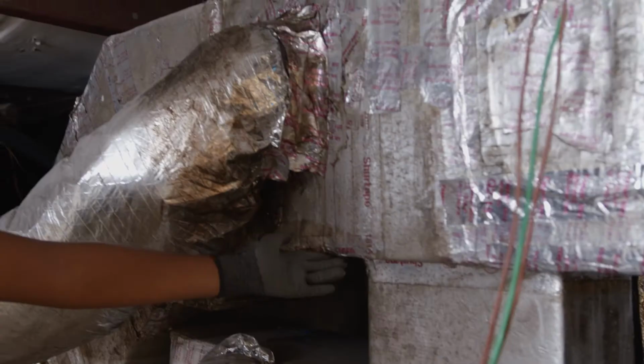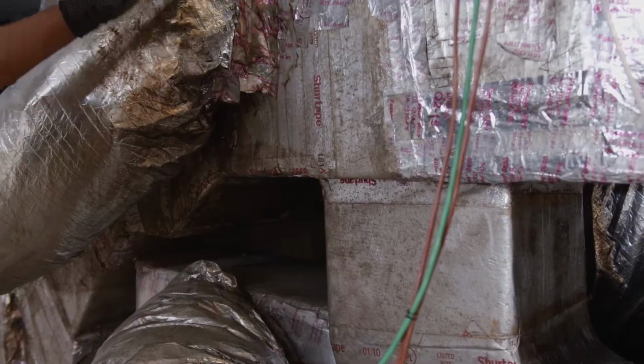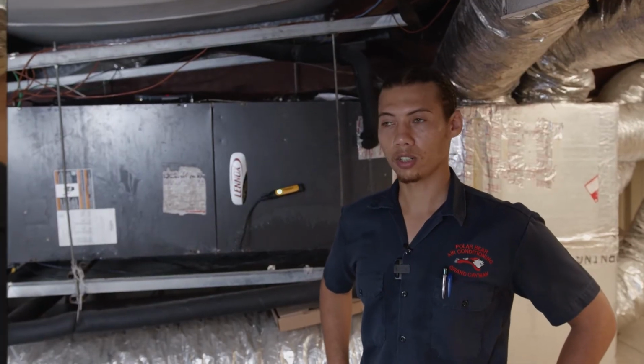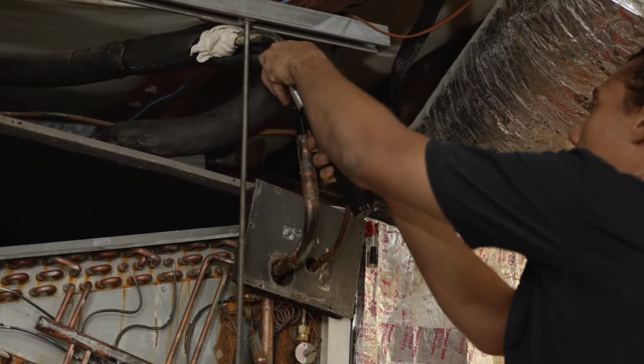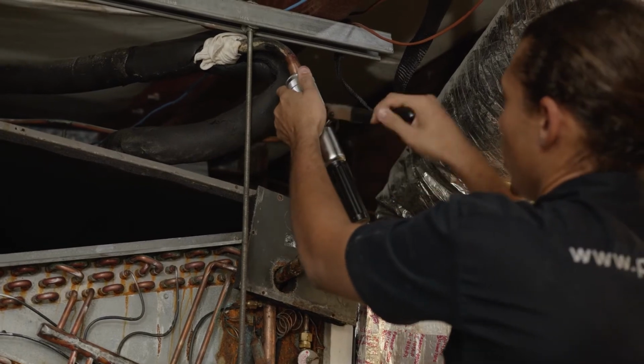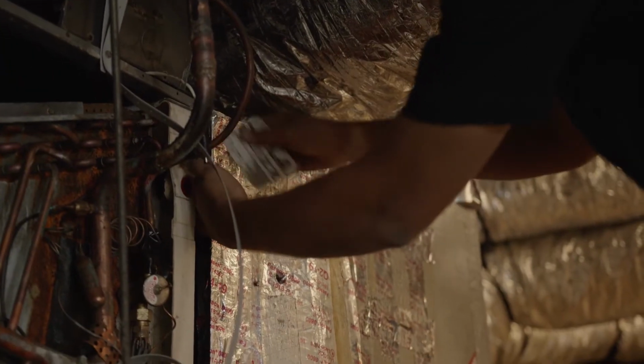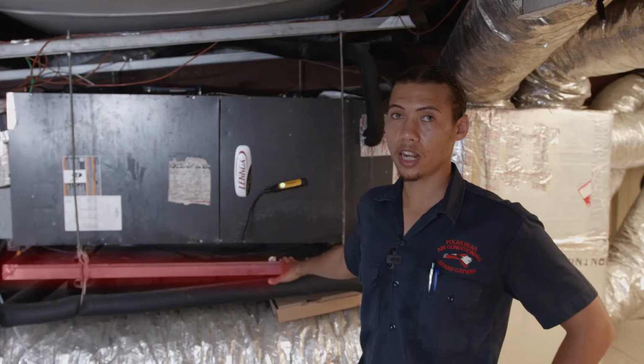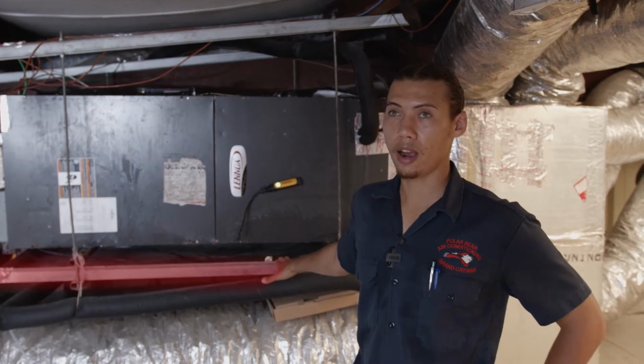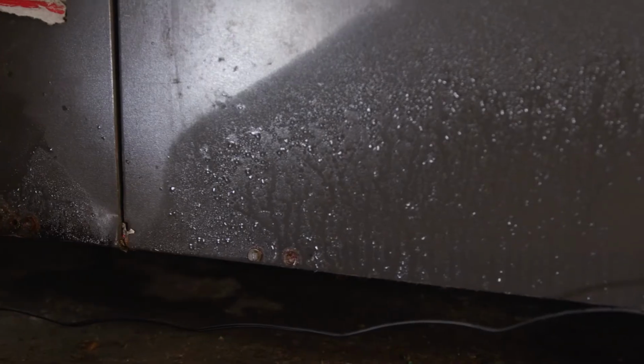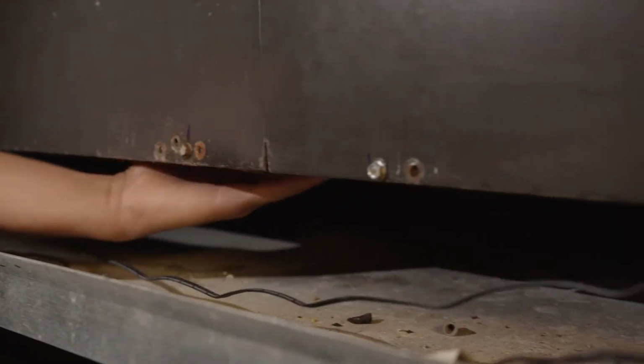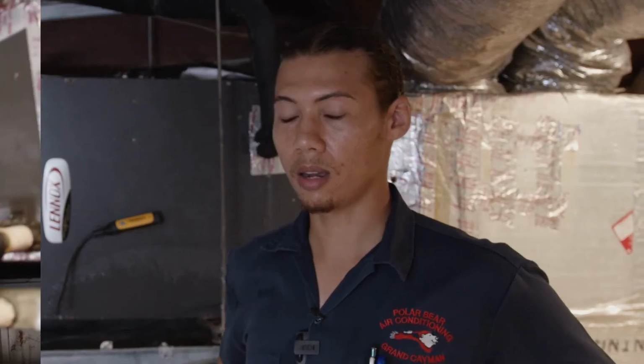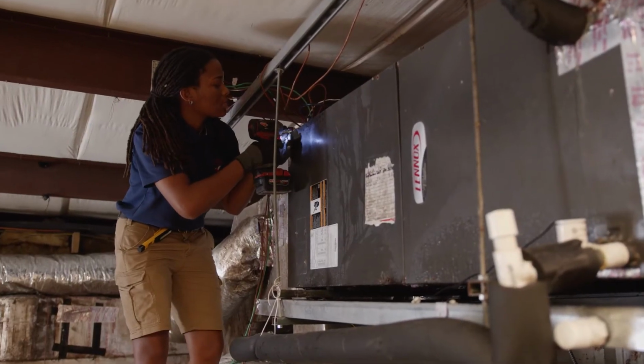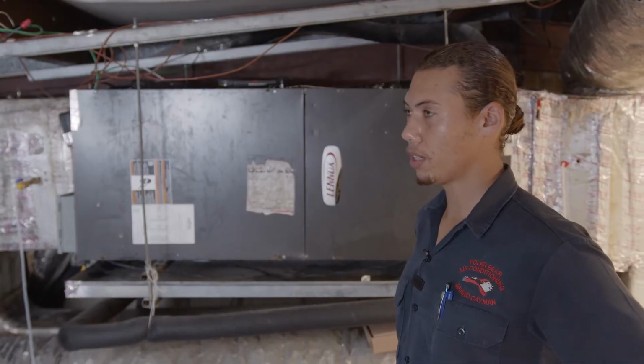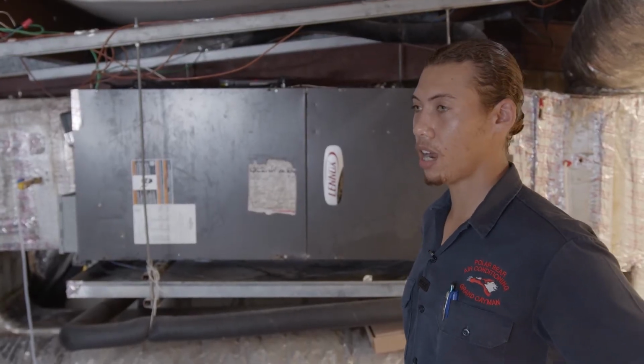And if the insulation is wet internally in the unit, it can actually cause biological growth concerns. So depending on what the issue is, it can actually cause your unit casing or your external drain pan to prematurely rust out. If you don't have safeties, it can cause the emergency pan to overflow and cause water damage.